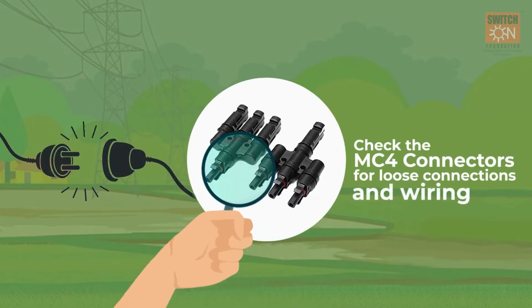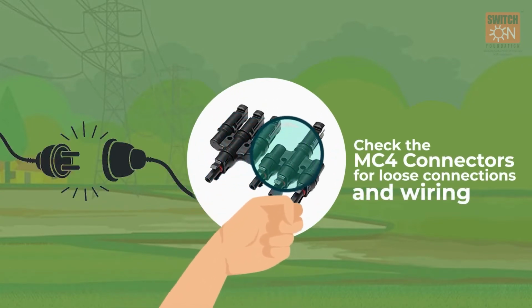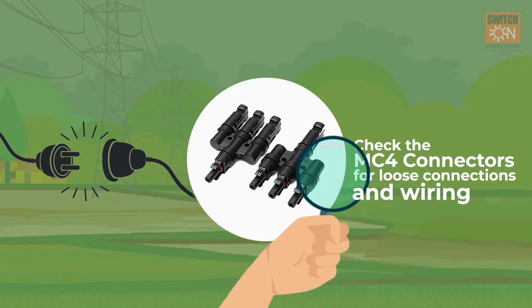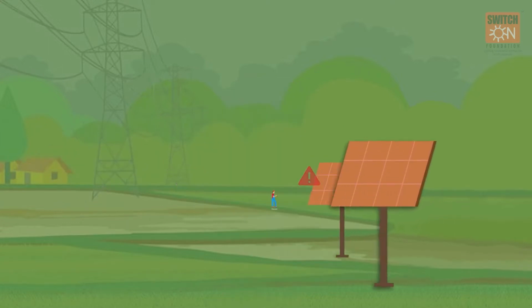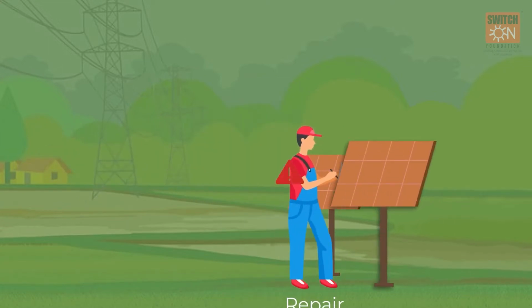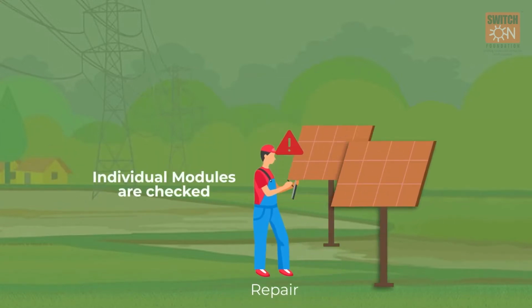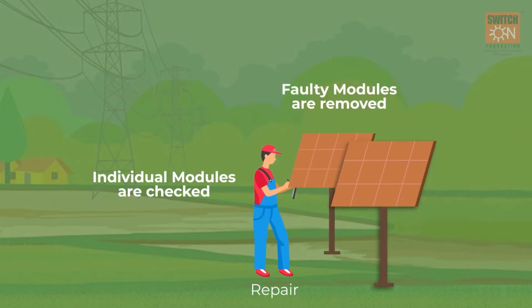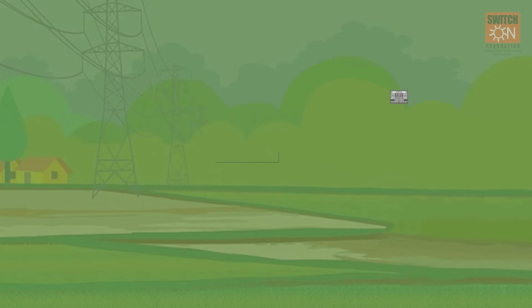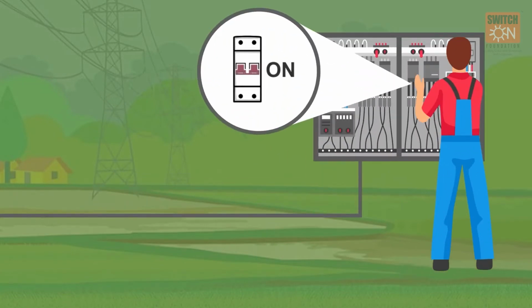3. Check for any loose connection in wiring or MC4 connectors. If any loose connection or faulty connector is found, it needs to be repaired or replaced. If the problem still persists, then individual modules need to be checked using a multimeter and the faulty module or modules need to be replaced.